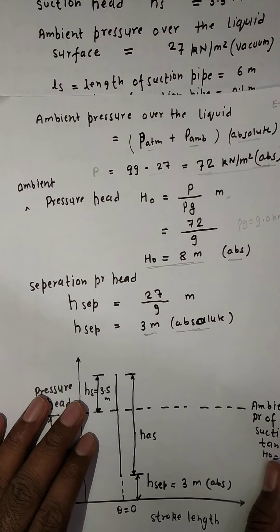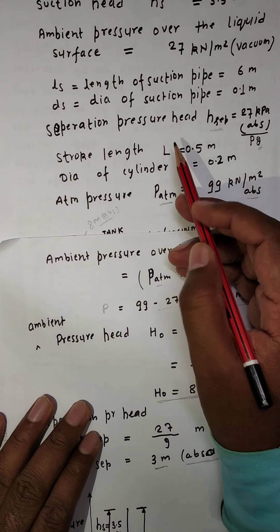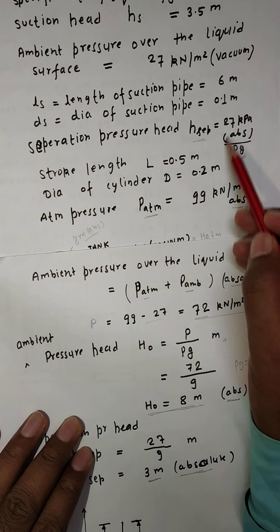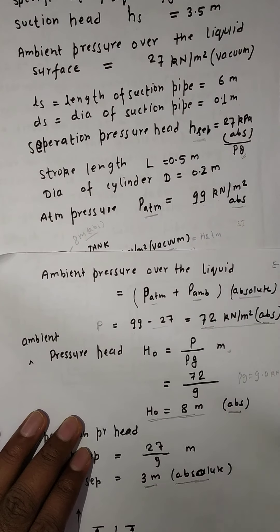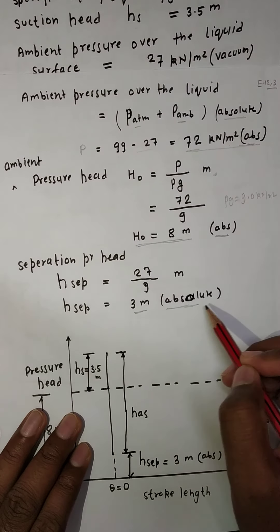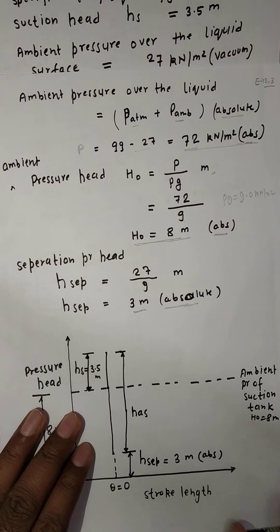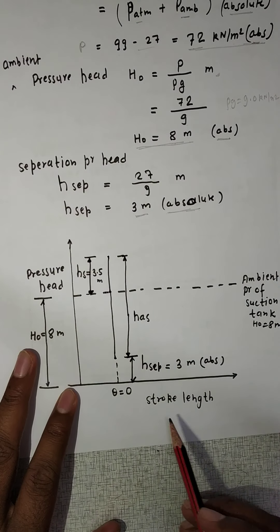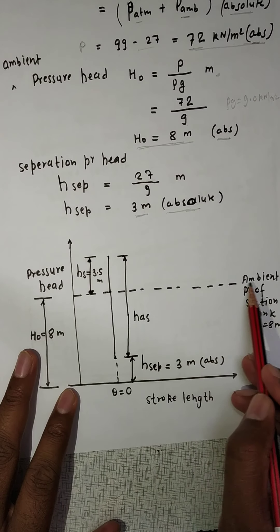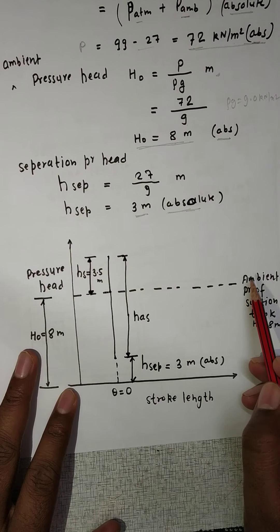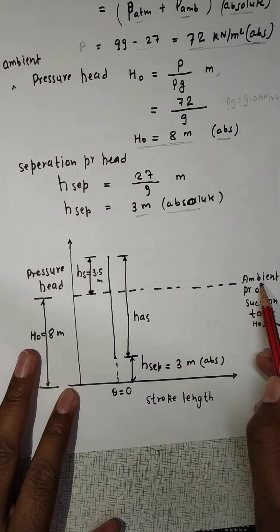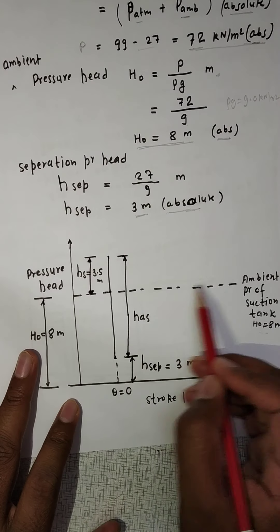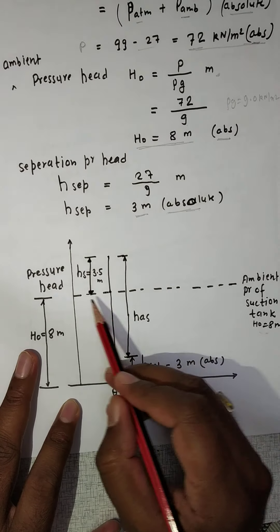The separation pressure head has been given as 27 kPa absolute. Dividing by rho g: 27 divided by 9 = 3 meters absolute. Now, this is the indicator diagram, drawn between pressure head and stroke length. The atmospheric pressure line and the ambient pressure of the suction tank is 8 meters — this value gives the pressure above the liquid surface.